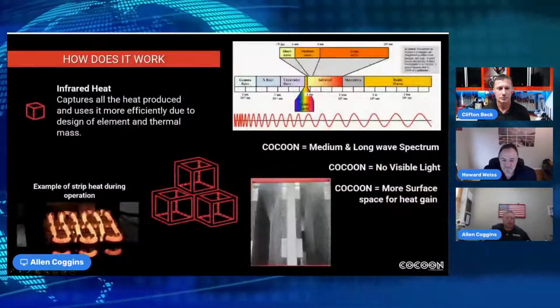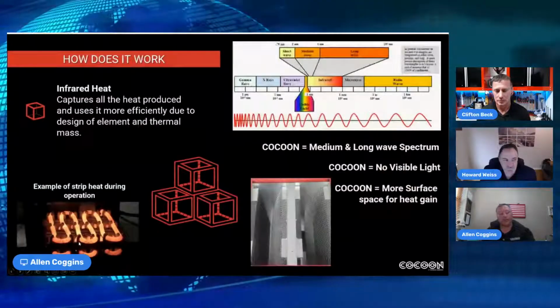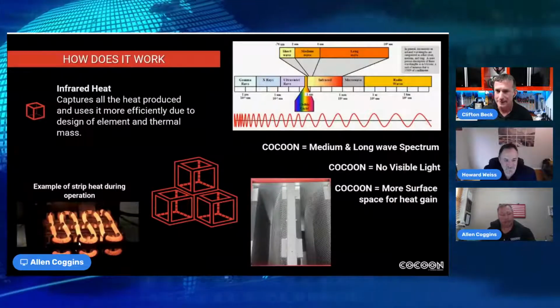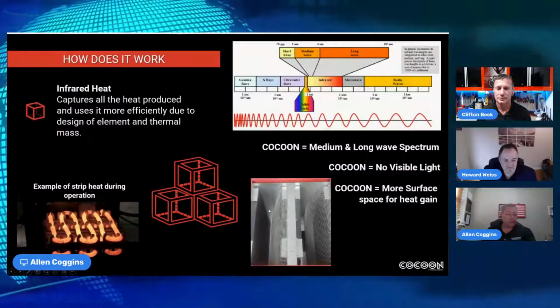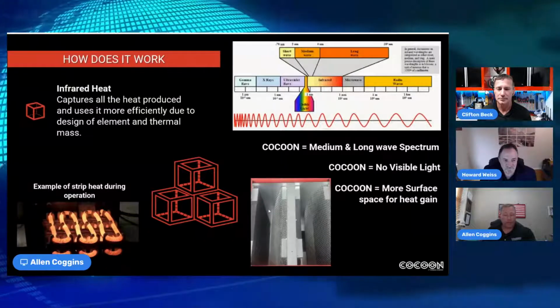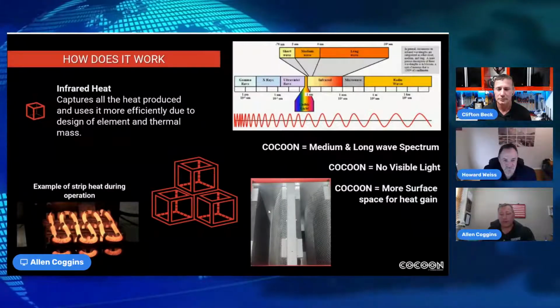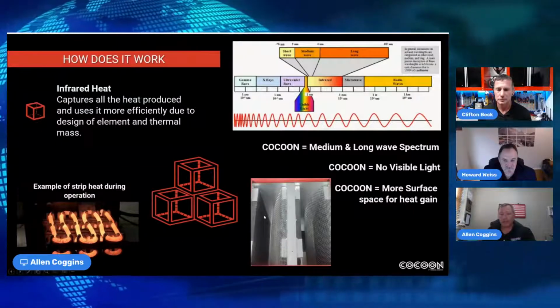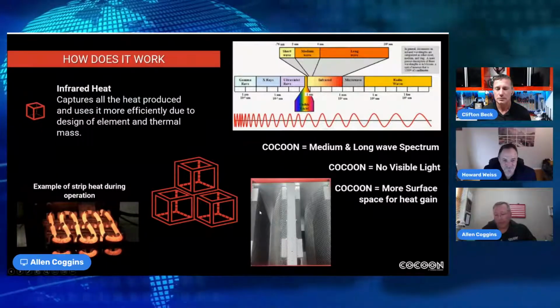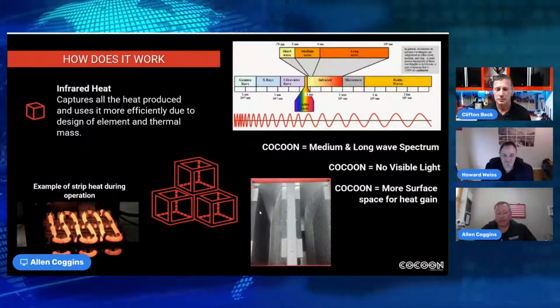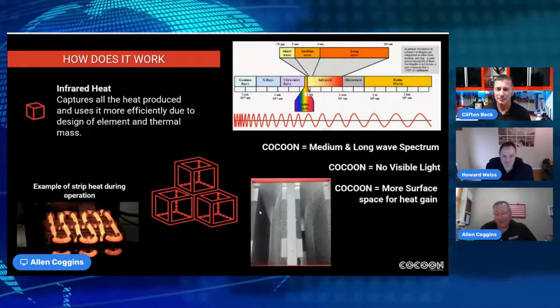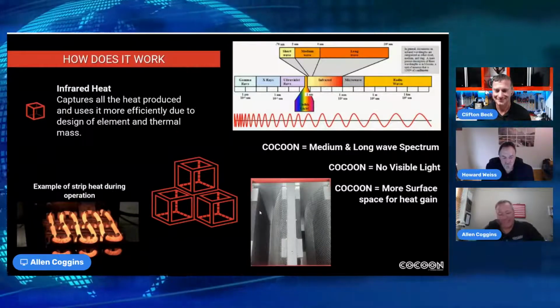If you go back to that open coil system, if you lose your airflow, you're going to burn that out immediately. With ours, you could technically, and I don't recommend this, run it like a gravity furnace and let gravity take its course. You can run these panels all day long with no air on them, but of course we don't recommend that. No air on them.